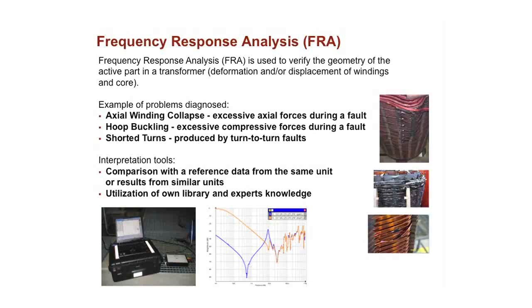So this is very good if you think there's been some kind of fault on the transformer. You can see if there's been changes in the windings. It can also, often, verify that nothing's happened. So, I mean, this is good to know as well.